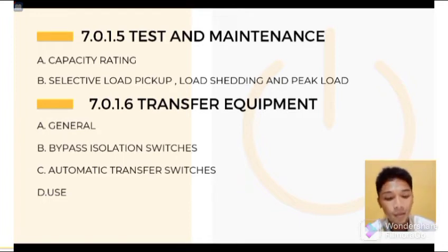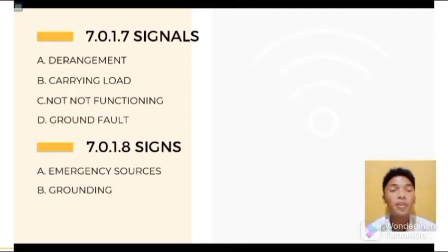Bypass isolation switches. Means shall be permitted to bypass and isolate the transfer equipment. Where bypass isolation switches are used, inadvertent parallel operation shall be avoided. Letter C, automatic transfer switches. Automatic transfer switches shall be electrically operated and mechanically held. D. Use. Transfer equipment shall supply only emergency loads. 7.0.1.7 Signals. Audible and visual signal devices shall be provided, where practicable, for the purposes described in 7.0.1.7 through 7.0.1.7d. Derangement.